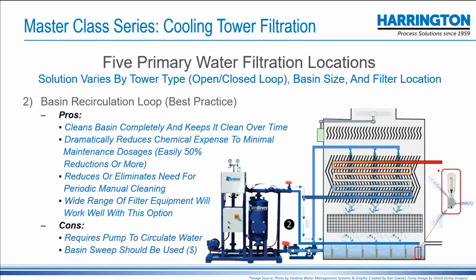An example is Harrington provided some years ago, about 8 years ago, a couple of filter units to Long Beach Medical Center out in California. They had a huge problem with sludge and algae buildup in their basin. And so they cleaned the basin, put in a recirculating filter. I honestly don't know if they put in the agitating spray nozzles. I know we recommended it. I checked on it about 4 or 5 months ago. They've been in operation. They have not had to clean out that basin once in 8 years' time. They were cleaning it out every 3 months because of the buildup they had before. So it was a highly, highly effective system.